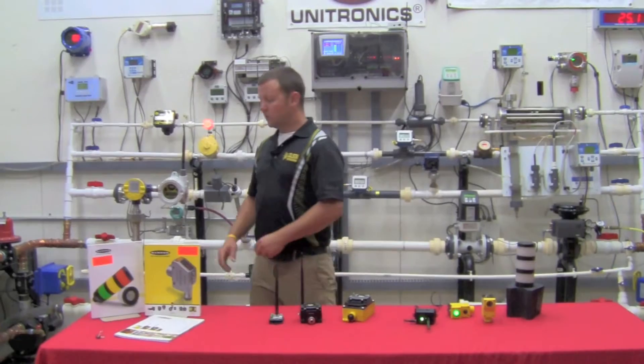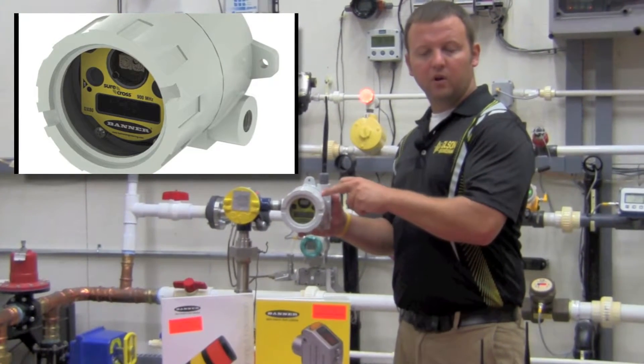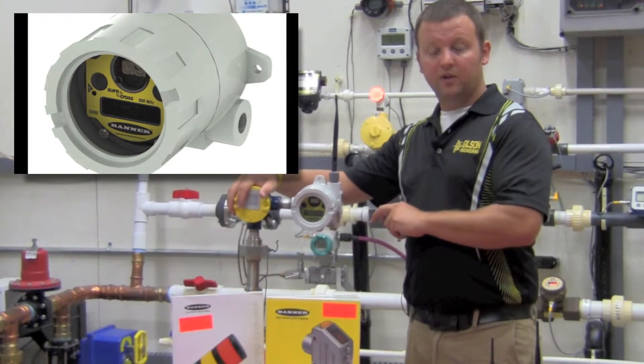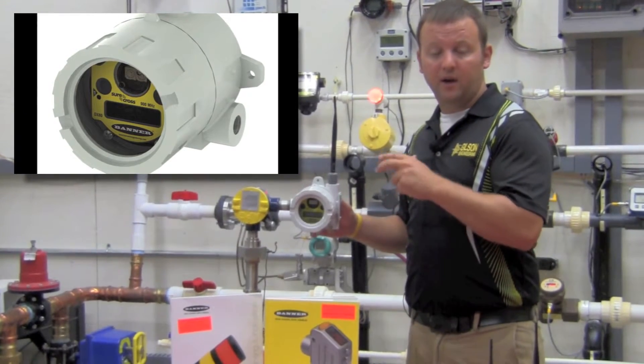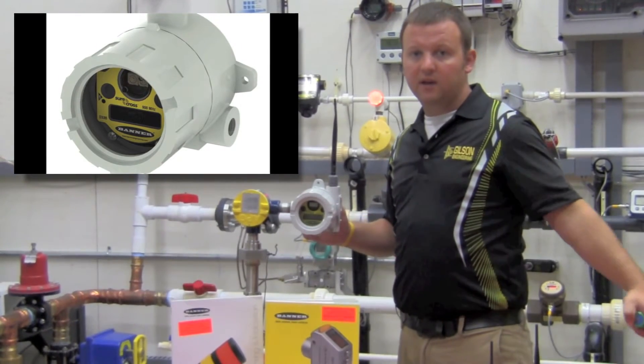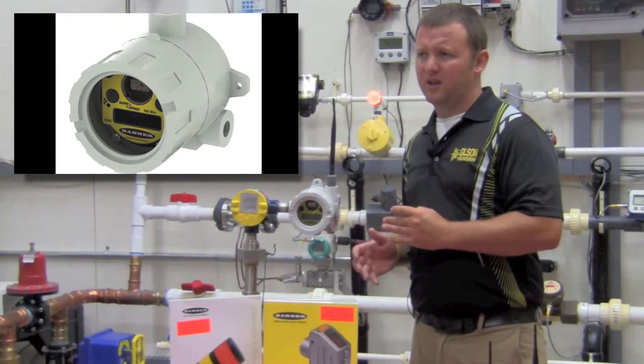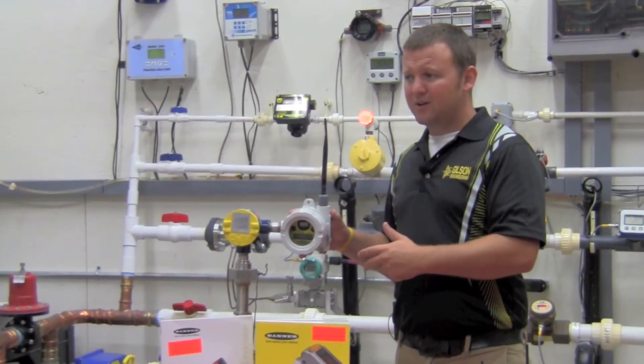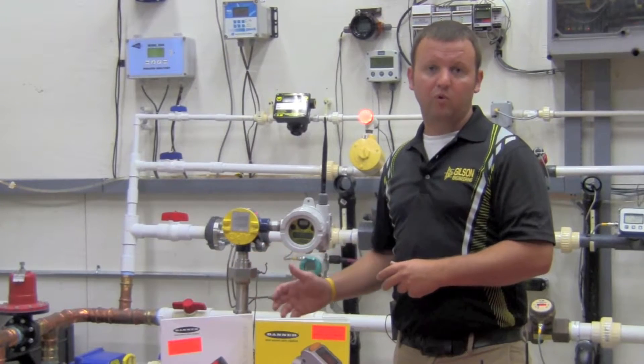Banner has also developed a hazardous area rated radio. It's a full metal enclosure with an intrinsically safe radio inside that can be coupled to an intrinsically safe field device for mounting in a Class 1 Div 1 or Class 1 Div 2 area. The radio runs on the same 19 amp-hour lithium battery as the non-hazardous radio. At a once-every-five-minute poll rate, you can expect something like two to three years of battery life in an application such as a float probe or a pressure transducer.